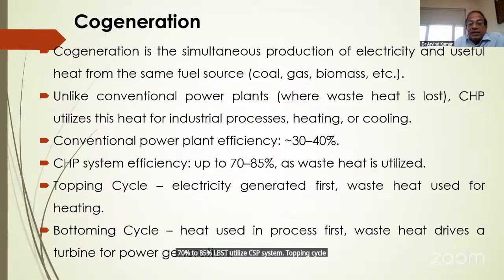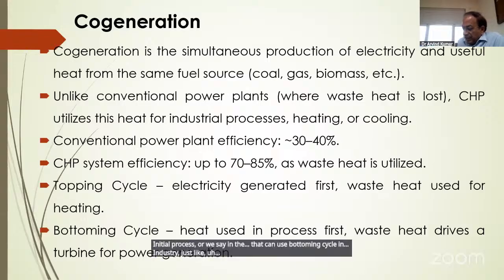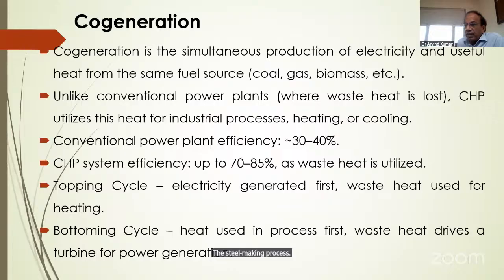Topping cycle: electricity is generated first and the waste heat is used for heating. Bottoming cycle: heat is used in the process first, and the waste heat drives a turbine for power generation. The bottoming cycle can be used in industry, for example in the steel making process, where furnaces have very high temperature. First the heat is used for the process of melting, then the waste heat is used for steam generation and to run the turbines.